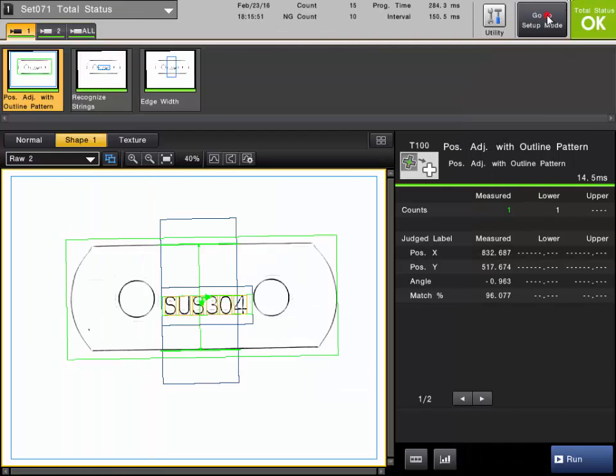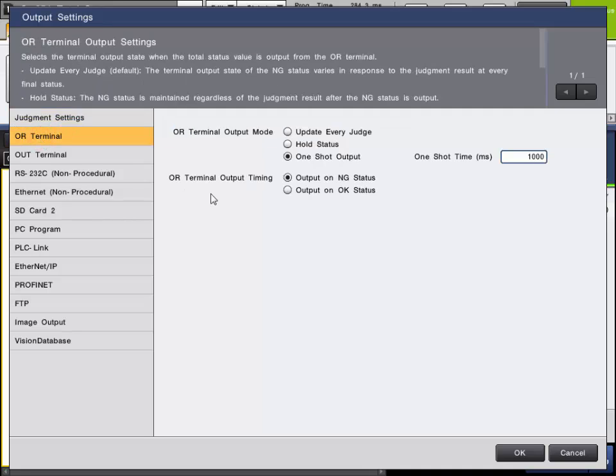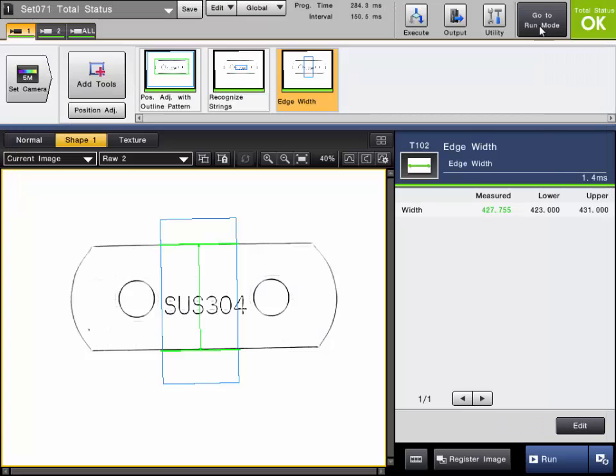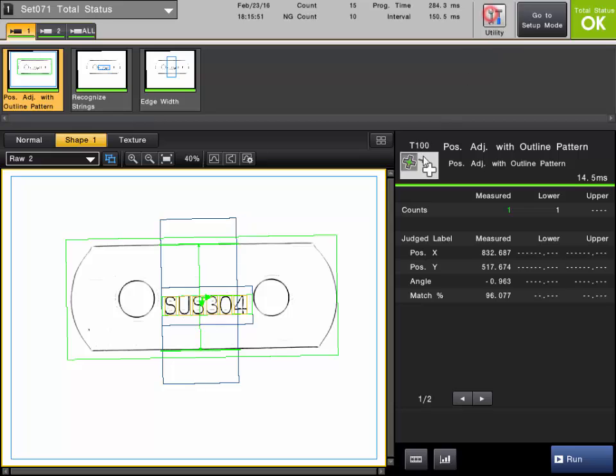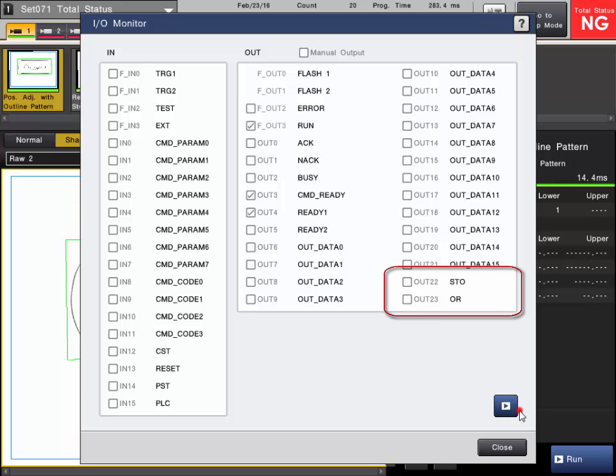If you want the opposite — turn on for an OK part — simply change the checkbox to output on for OK status, keeping the one shot time at 1000 milliseconds. In run mode with the IO monitor: triggering on a good part, you can see we get that one shot pulse for OK. Every time we have an OK, we get the pulse. If we have a no good condition and remove the part, the OR does not turn on — we only get this pulse for an OK condition. That's the total status output.